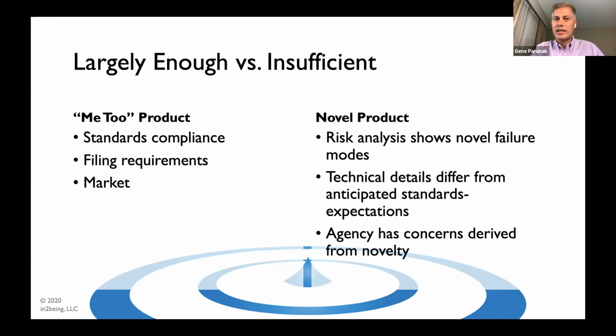But an awful lot of companies I know are developing truly novel products. They're not looking to be Me Too—in fact, if they were, investors probably never would have invested in those companies. So risk analysis is going to show novel failure modes. The technical details of your new product may differ from those anticipated in standards written for similar devices. Or maybe the FDA has concerns that come out of the novelty of your new device. In this case, standards compliance may be necessary, but it's usually insufficient to get you all the way across the finish line.